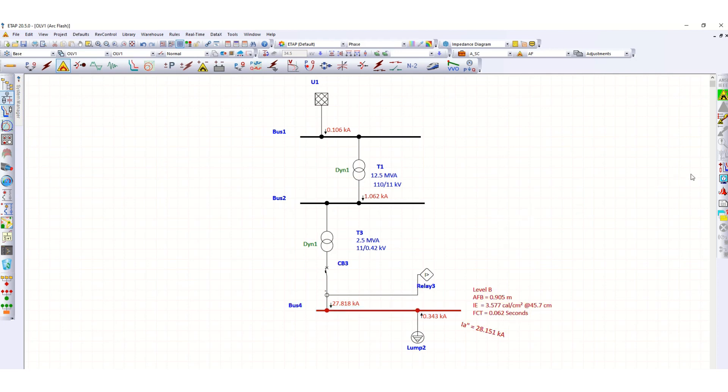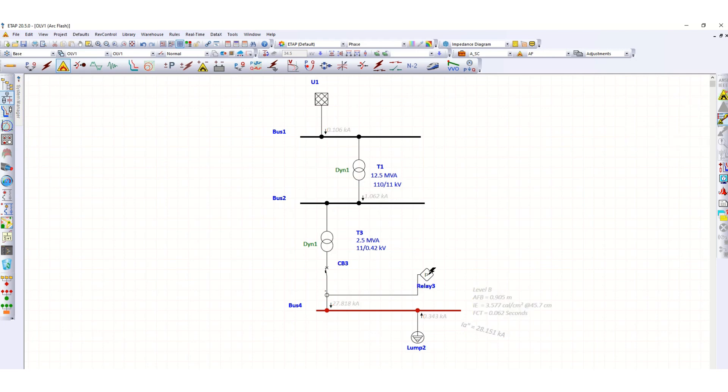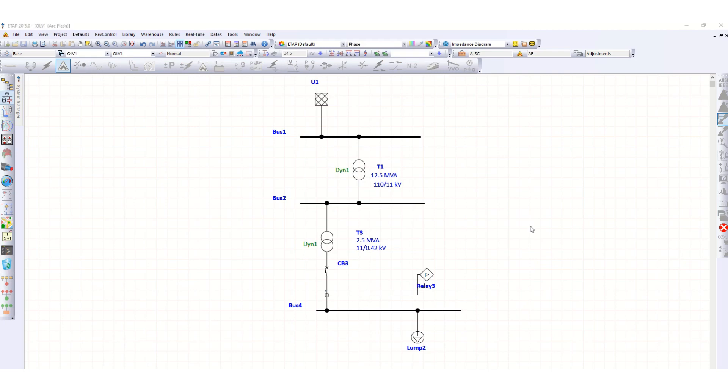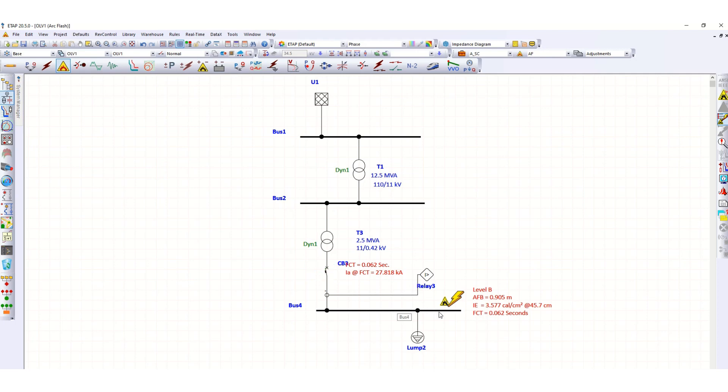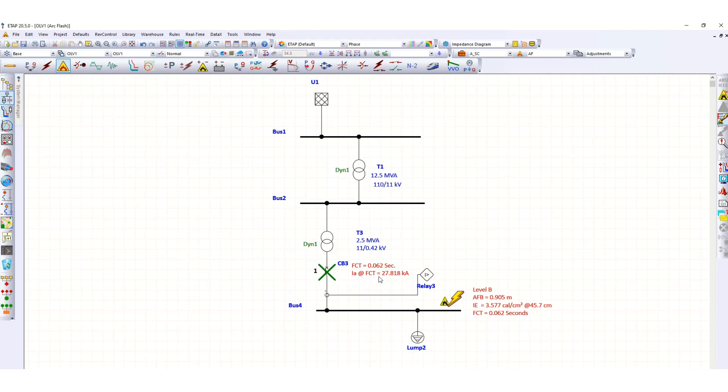Let's insert this fault sequence operation. You can see in case of any Arc Flash over here, the protective device CB3 will open. The fault clearing time is 0.062 seconds at 27.818 kilo ampere.